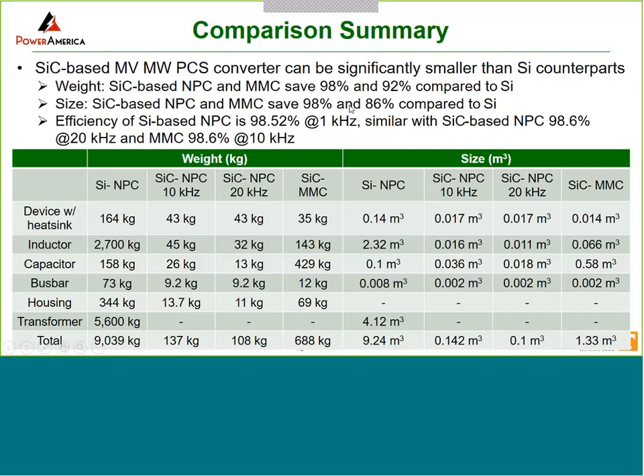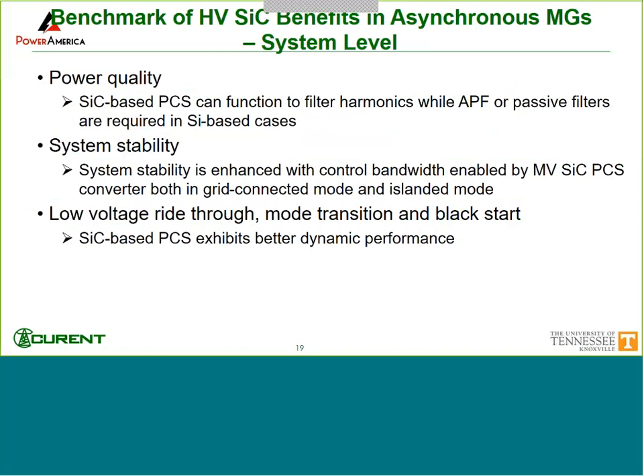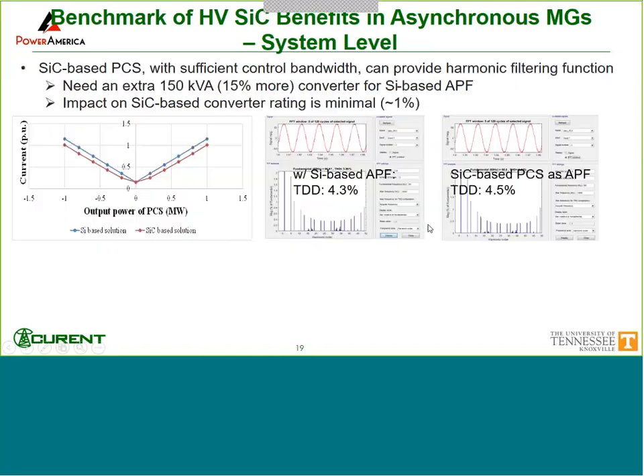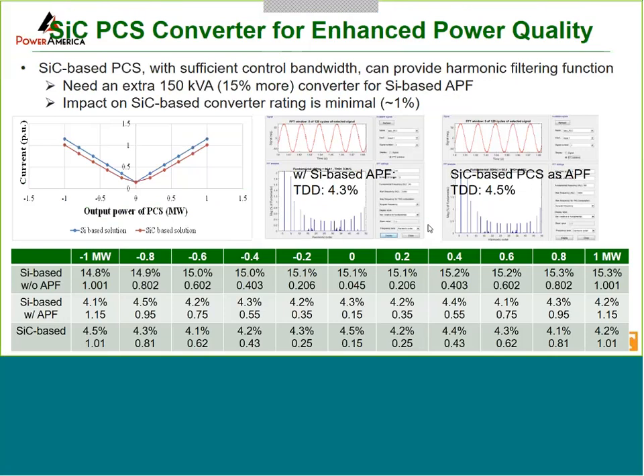Of course, the loss in this case, we pick them to be the same. They are not the main thing. The main thing is actually the passives. So that's the converter level. At the system level, we look at the power quality, the system stability, low voltage ride-through, mode transition, and black start. We go one by one. These are all simulation work.